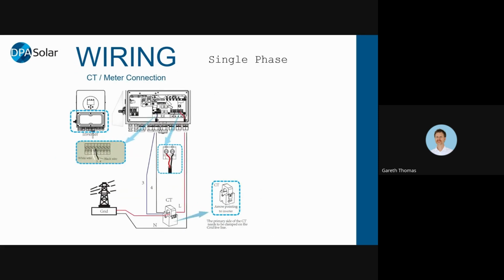For the CT connection, it comes with a CT. For the single phase inverter, you can see that there is a set of push-in connectors on the main board here. Each one of these has a number, and your CT is going to go into numbers 3 and 4. You just push those in, and then you're going to put that CT around the active from the grid. And the arrow on the CT should be pointing towards the inverter. So it comes with that CT in the box.